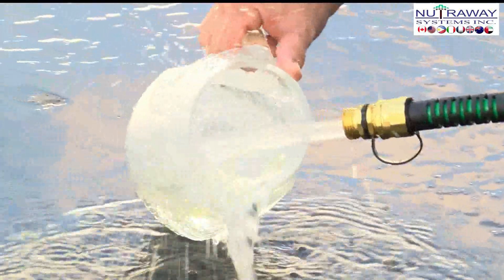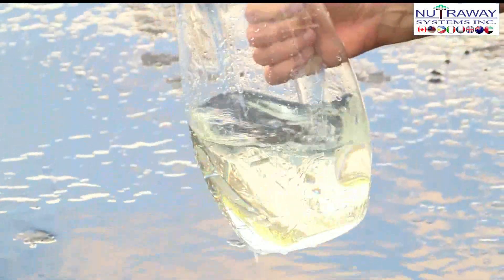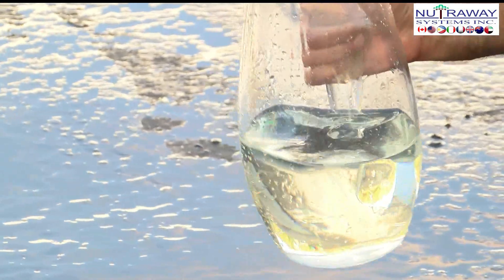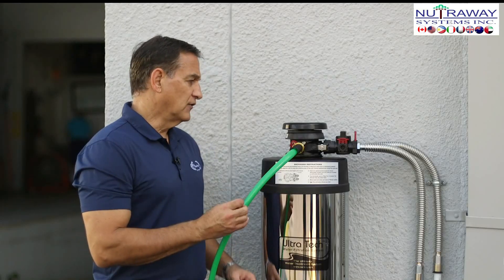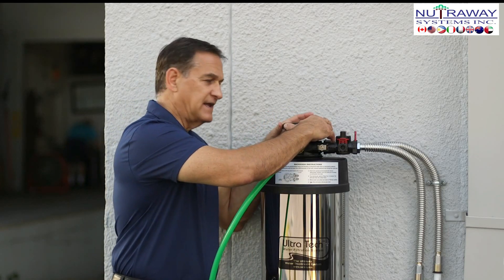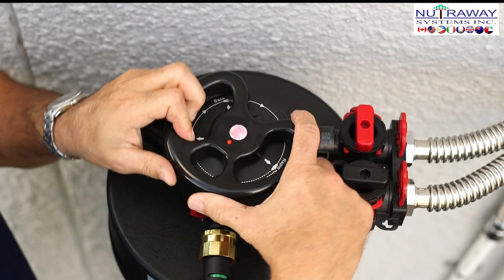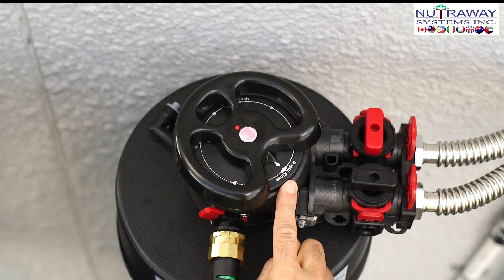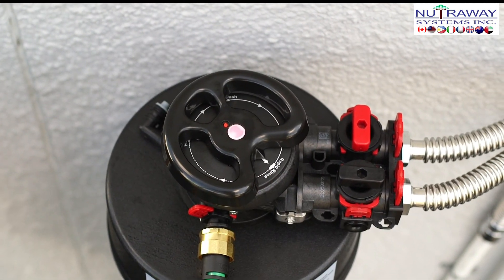Now that the water is coming out clear, we can move to the next stage of the backwash, which is the fast rinse. In order to do that, we simply take the handle and move it clockwise until we reach fast rinse. We'll leave it on fast rinse for about 10 minutes.